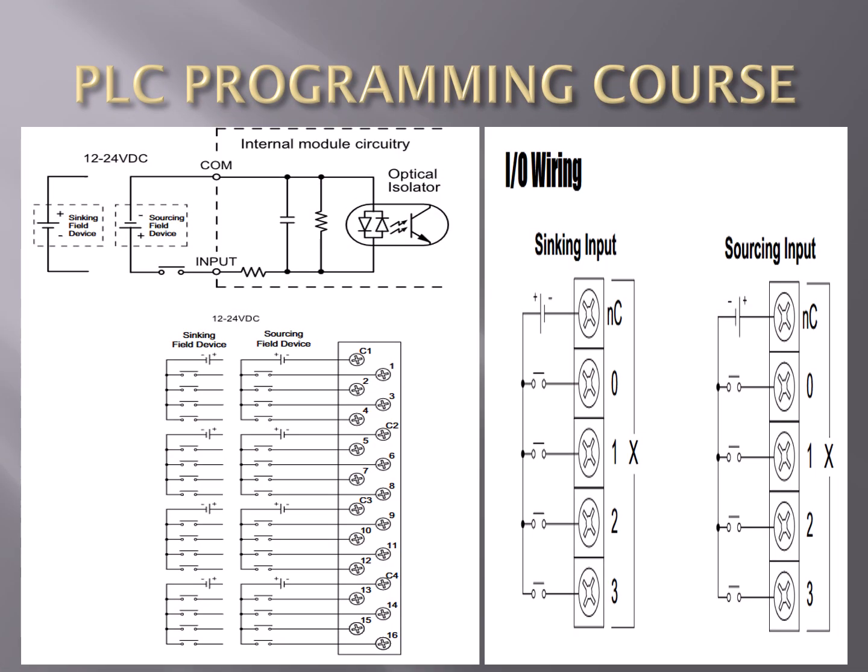So here they are side by side, and you can see the differences in the two connections and the nomenclature involved. When the positive is connected to the commons of all the push buttons and then bringing positive into the input, it's actually called a sinking input on the component side, but it's a sourcing field device.